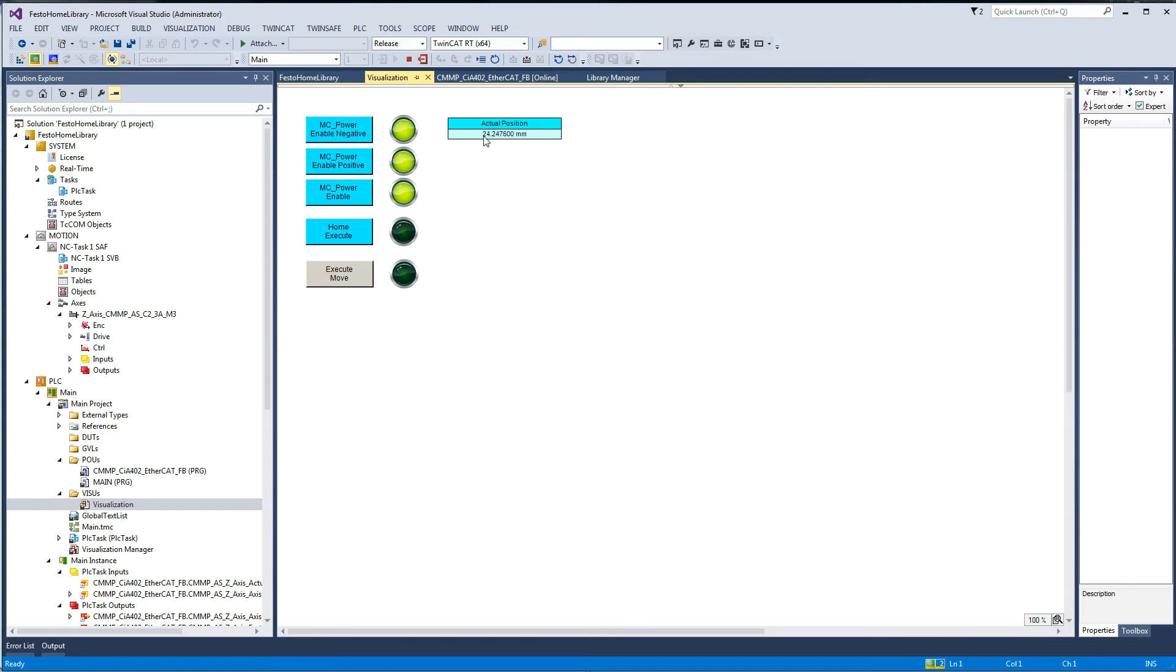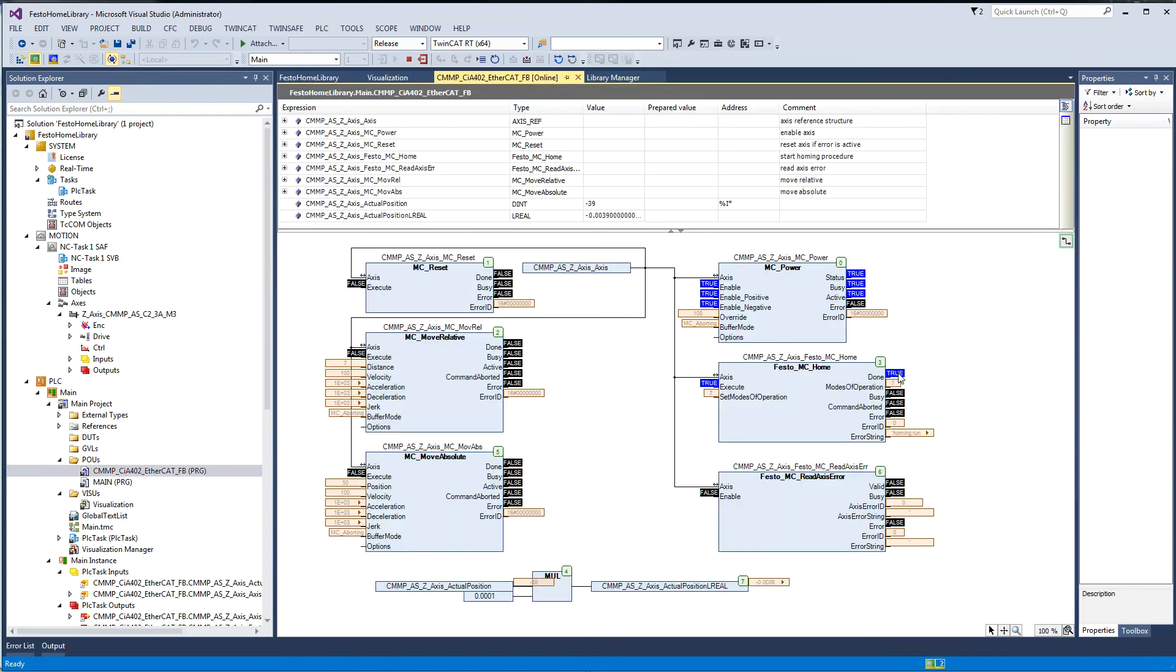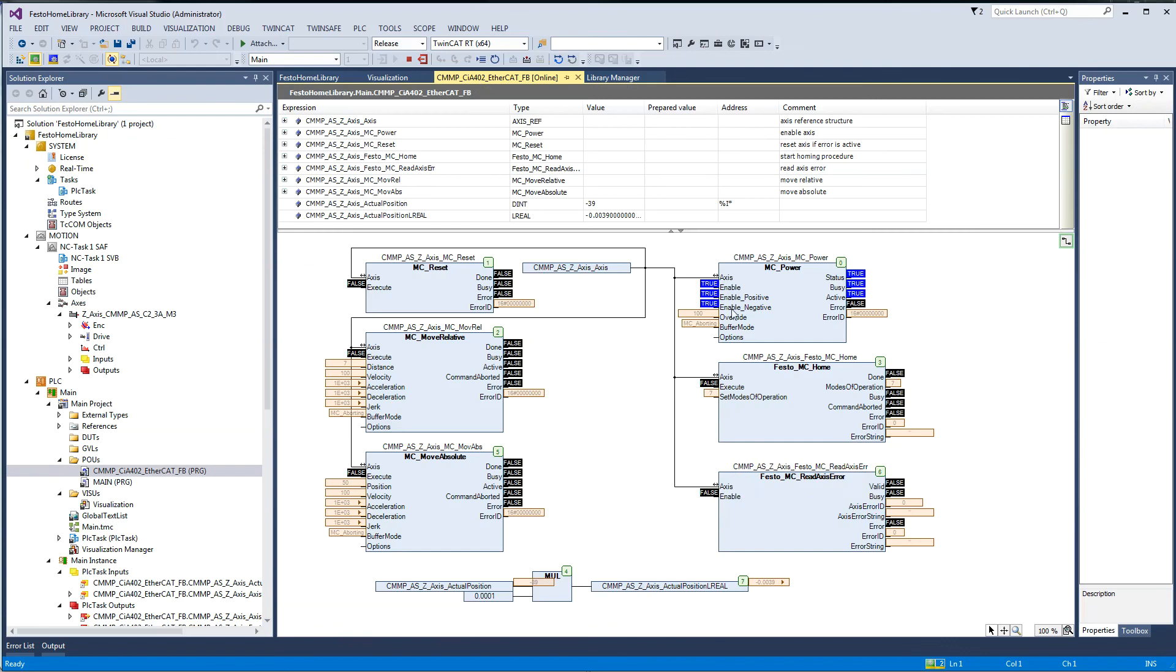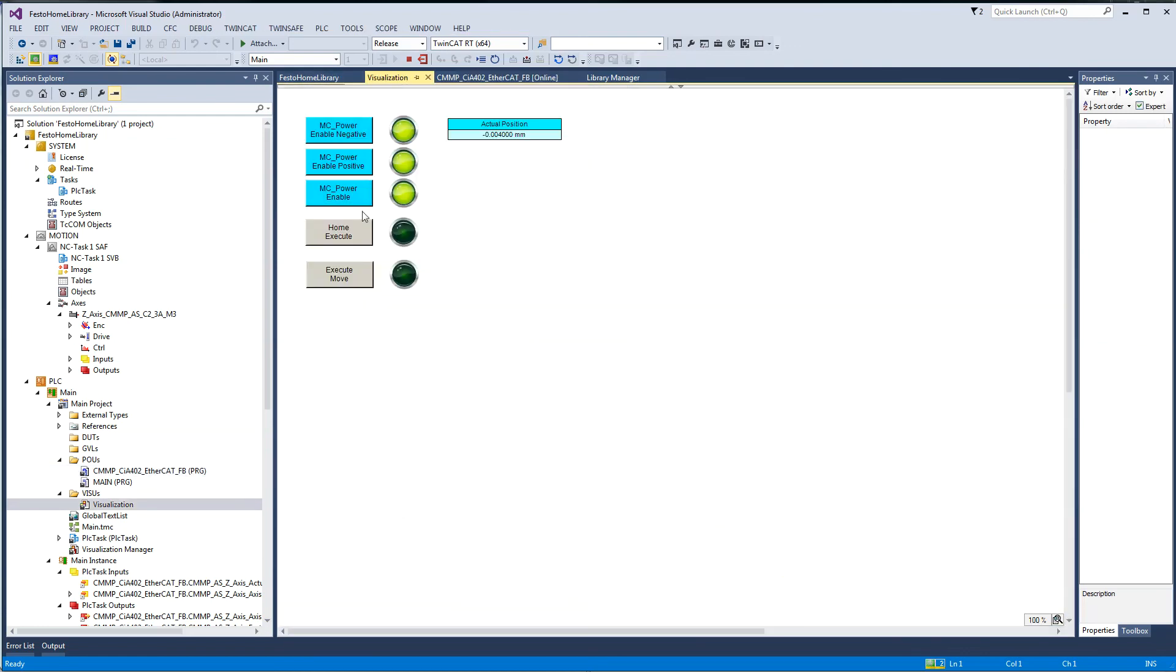There's my 50 millimeters position. I'm executing a home and it's going towards home and it homes, then it gives me the done. Now that that's done, I can execute a move. When I execute that move, it's going to execute this 50 millimeter move here. It just moved, went to 50 millimeters here, and we're done. That's how the Festo home library works.